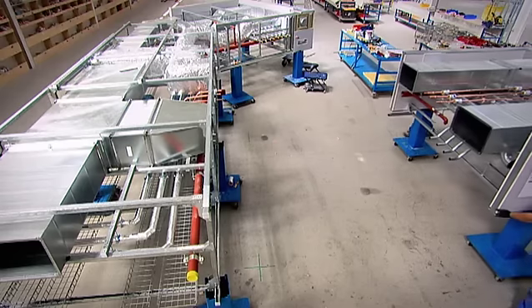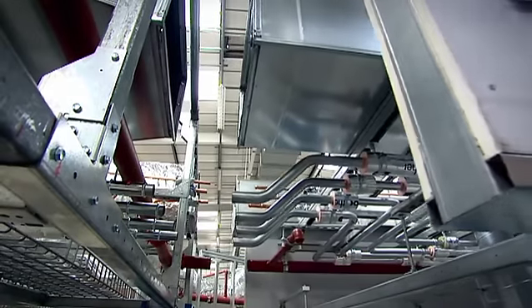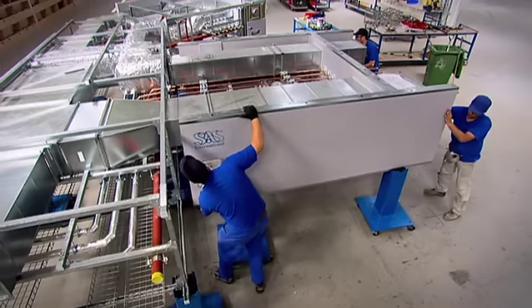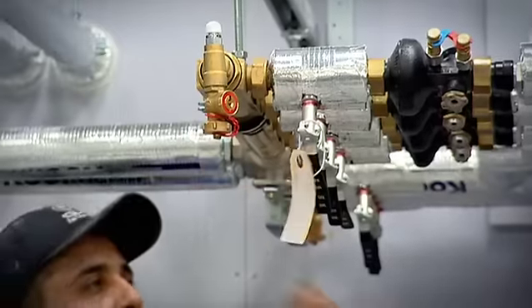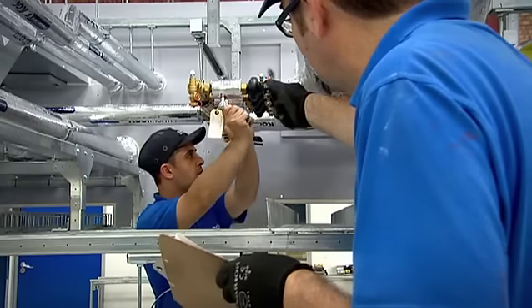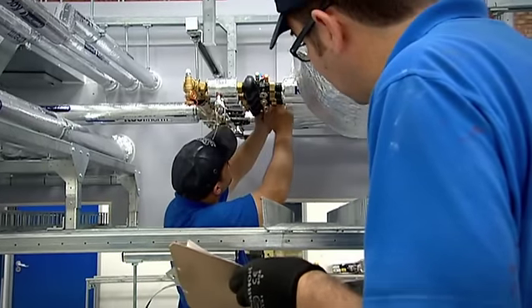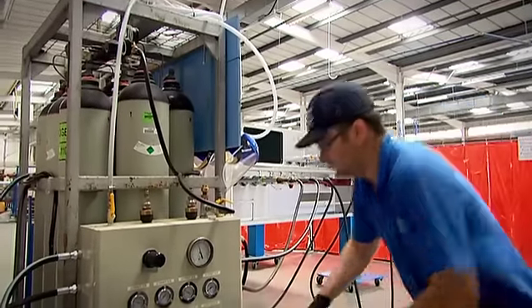Modules are manufactured together in sequence, matching the planned floor plate, and all pipe connections within the modules are tested. This helps to ensure on-site installation runs as smoothly as possible. Consistency is maintained by a rigid quality assurance program, where each module is individually inspected prior to testing and prior to leaving the factory. The checklist includes the testing of all module elements and apertures, as well as the use of a high-pressure nitrogen gas system to confirm the integrity of all pipes and joints.